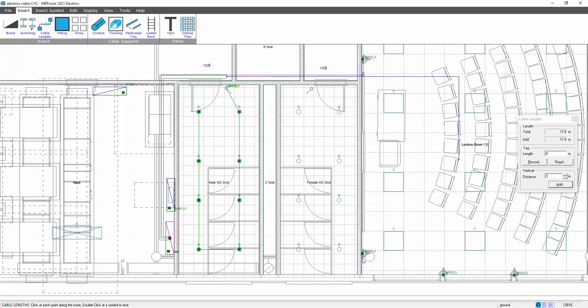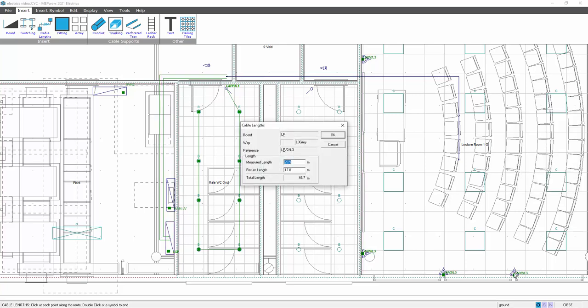You don't have to select every socket, all you do is put your real intended cable route in. So if I'm at skirting level, and I want to run round to this socket here, all I would do is enter the corner here, and then just double click on that final socket. And you see it gives me a measured length of 28 meters, but it does work out a return length horizontally and vertically to the board at 17 meters.